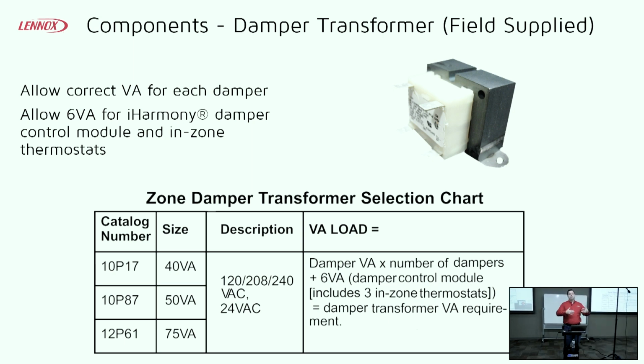Now, of course, if you have a much more complicated system, it's most common to have 1 damper per zone. But in some of these homes, that can be a little bit easier said than done, and so they have to add additional dampers. For each one of those dampers, you've got to do the math and figure how much power they're consuming and make sure, okay, I might need a little bit bigger transformer. So you might have to sub that in. You can actually do a couple of different transformers if needed. Again, it's not very common, but if it's necessary, there's a diagram in the presentation that talks about that. A lot of this information is either going to be in the installation instructions or the product specification. Any questions about that?